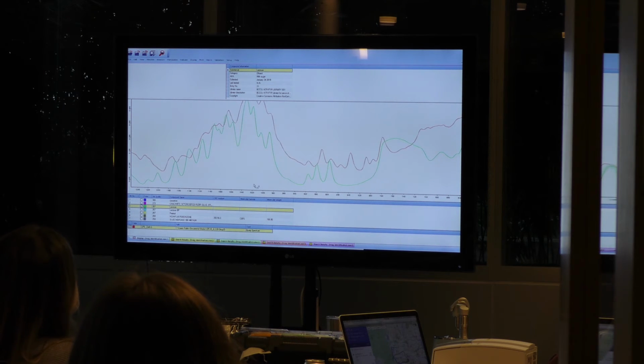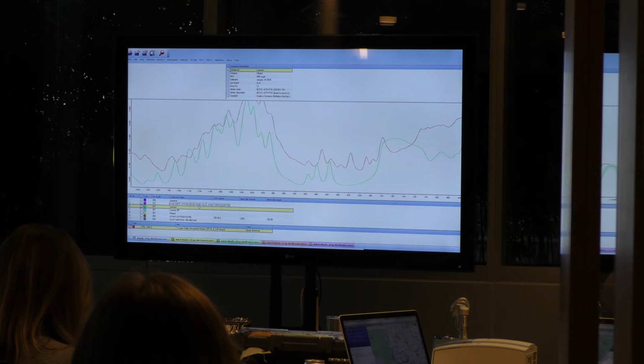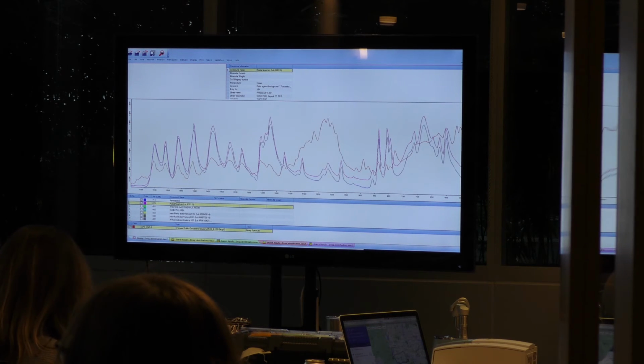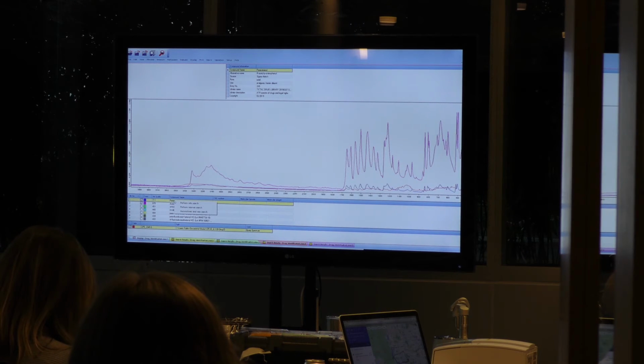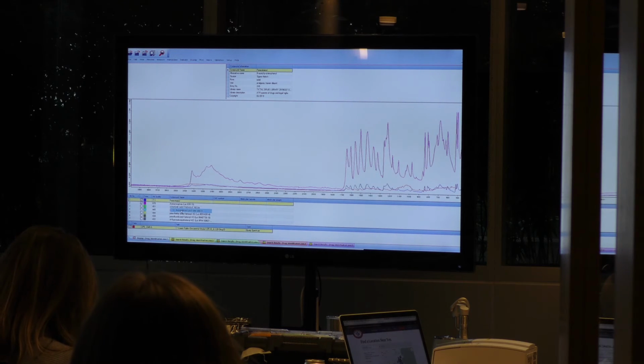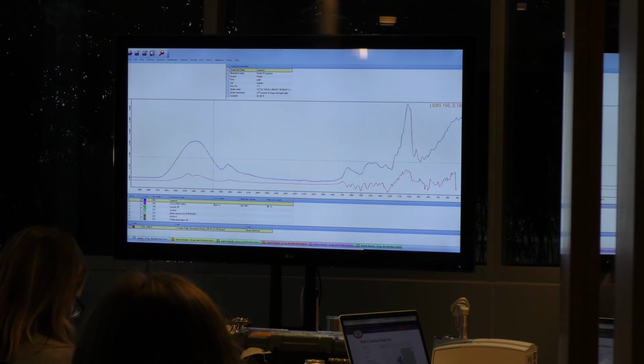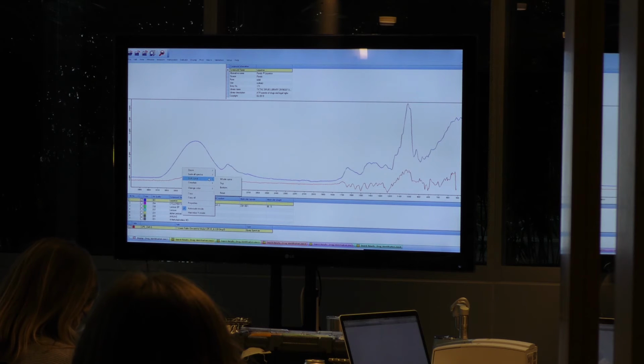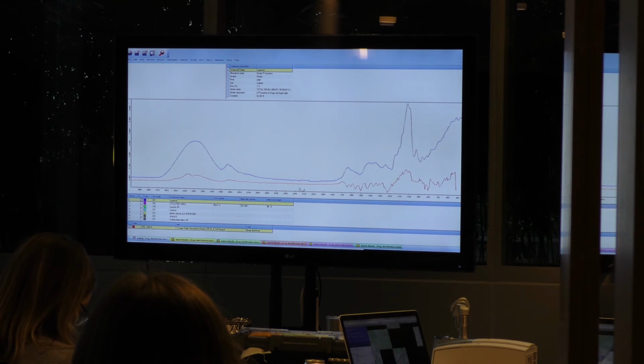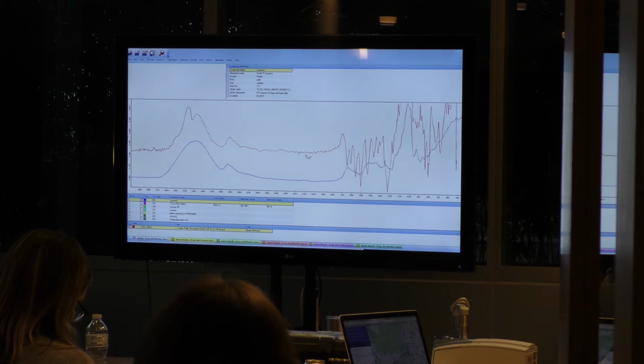So you don't do the subtraction method, right? Is there a reason why? These are two legitimate approaches, right? We would still use this, like search specific keys, but is there a reason why you don't do the subtraction method? Because at least that I found, I think I gave up on it very quickly. So auto subtract a new search is that other option. We're pretty sure it's paracetamol, so we can go auto subtract a new search and it'll take the subtraction of the spectra and tell you what's next. But the problem that I always see is it bottoms out something, it over subtracts something. Yeah, of course it does, right?